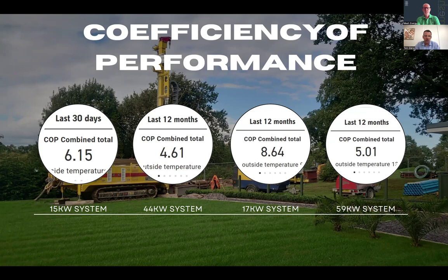So there are certain parameters which are set in the hot water cylinder and a buffer tank. The heat pump will wait for the temperature to drop in the buffer tank by, let's say, 5 to 10 degrees, so it's not starting all the time. So it says, today, 15 degrees outside, let's maintain the temperature in the buffer tank of 28. It will wait for the temperature to drop to, let's say, 23. When the temperature drops to 23, the heat pump will start again, warm up the buffer tank to 28, and will switch off. Then it will look at what's going on in the hot water cylinder.